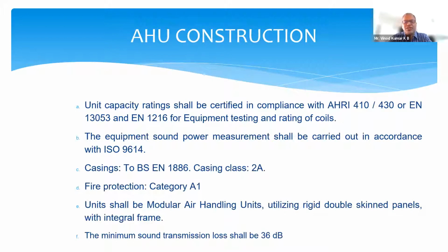Now I'm going deeper into the technicalities of the AHUs. How do you select the AHUs? How should the AHU construction be? The AHU construction for a healthcare system is very specific as far as ASHRAE guidelines are concerned. So we have to make sure that you set up your design standards and your specifications very clearly even before you start purchasing, because what you get from the market could be a simple dabba, a box which just delivers air and cooling. It is not going to be that simple, because the healthcare AHUs are supposed to follow a set of standards, which I will be going through in the next few slides.